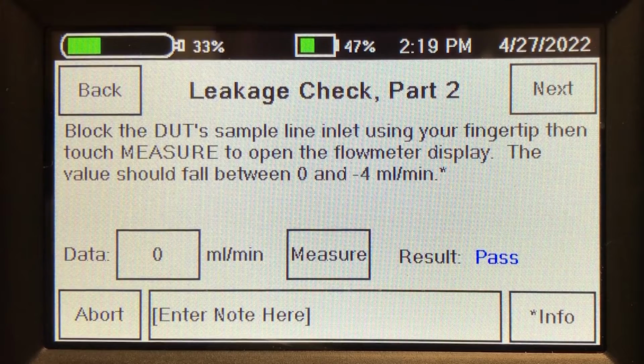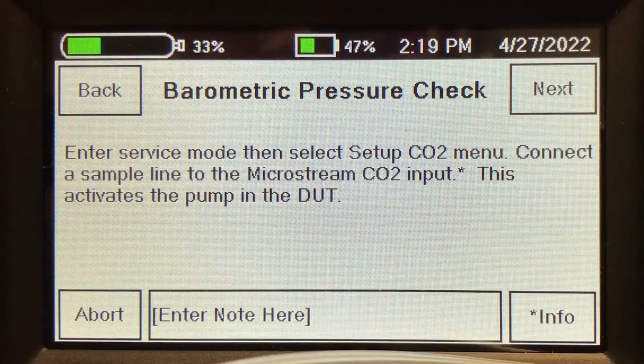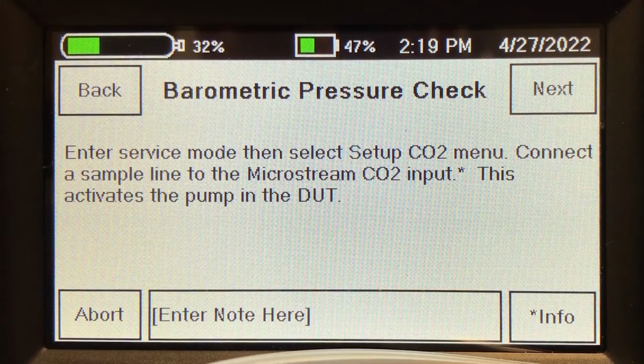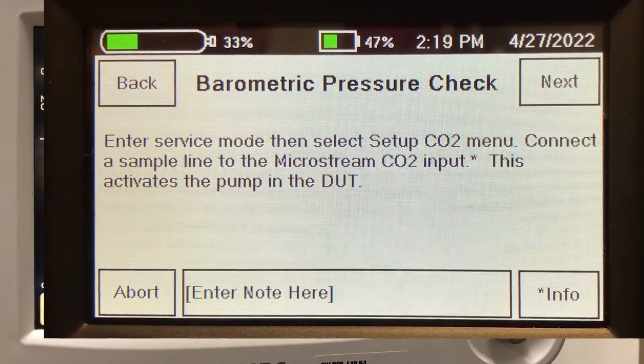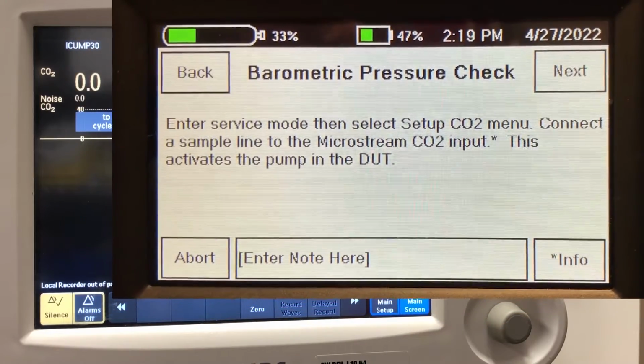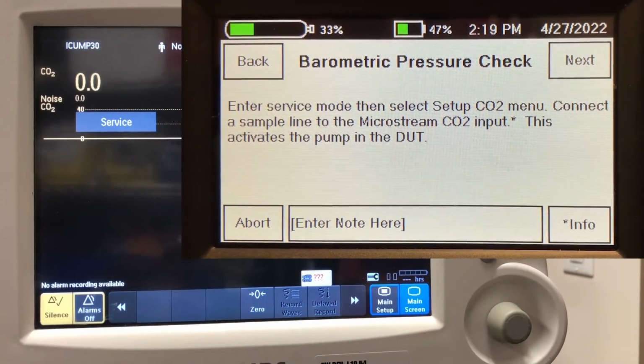firmware in this device is actually the one that requires us to take it out and do a leak down test, because the firmware change they made is that it instantly tries to clear the sample line rather than wait 25 seconds to do it. So this test method's really not the right one for this firmware revision of module. So next we're going to check the barometric pressure. We leave the sample line connected.